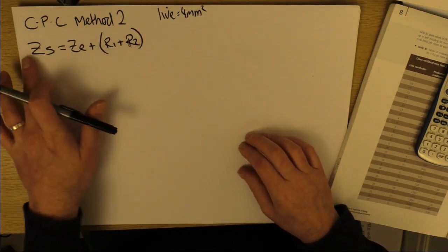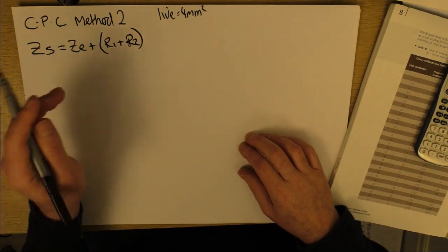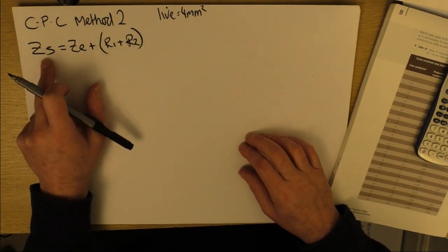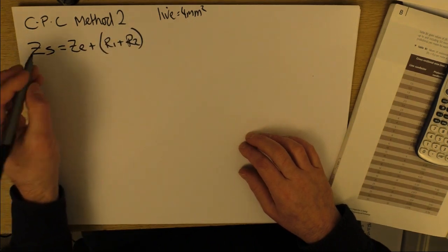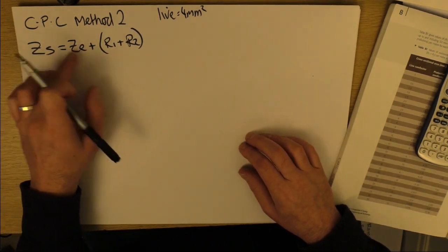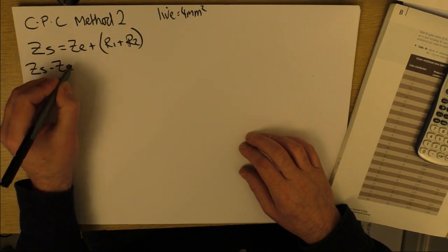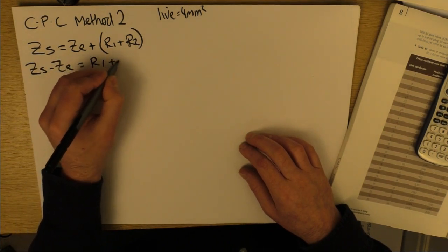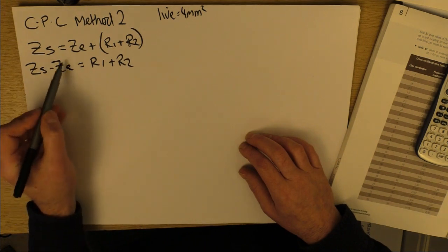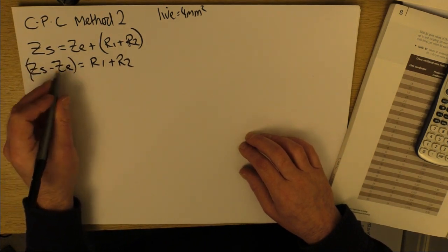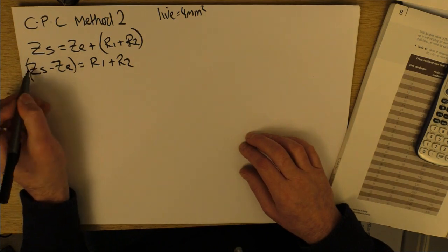So we need to kind of play with this and find out how to transpose this really to get maximum milliohm per meter. So first, we can get that ZE out the way. So that would end up like that. That's dealt with. We can also do that already. Now this is like the maximum ZS.